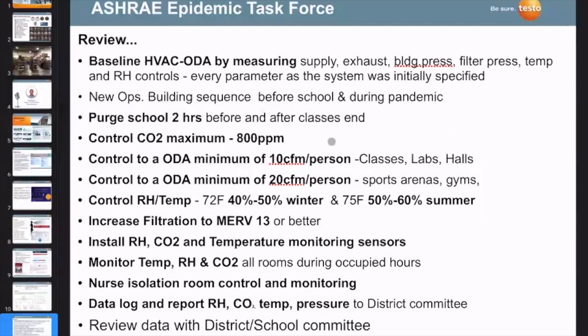Maintain, and do not exceed, 800 to 1,000 parts per million as a maximum number of CO2 in the occupied classrooms. And control that relative humidity between 40 and 60% RH, seasonally dependent, and also maintain the temperatures in this space in the mid to low 70s. Increase filtration to MERV 13, and we'll talk about that a little bit in a second. And then the installation of CO2, relative humidity, and temperature monitoring sensors in the classroom space, and that during all occupied hours, data should be collected from those three variables, documented, and submitted as a report to the district committee.